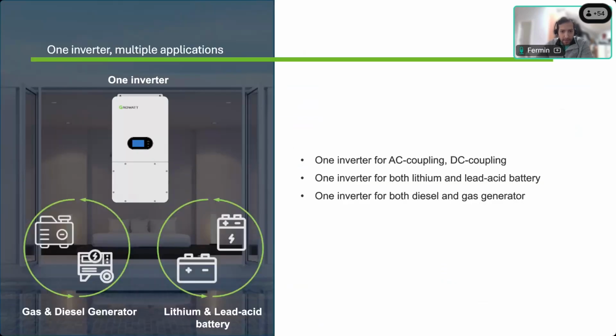As I mentioned before, this is a very versatile inverter. It allows for AC coupling, DC coupling, or both at the same time. It works with both lithium and lead acid batteries, and at the same time, it allows you to couple up to 10 kilowatts of diesel generator power.